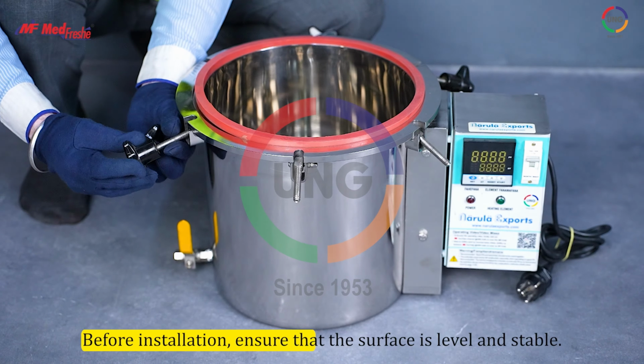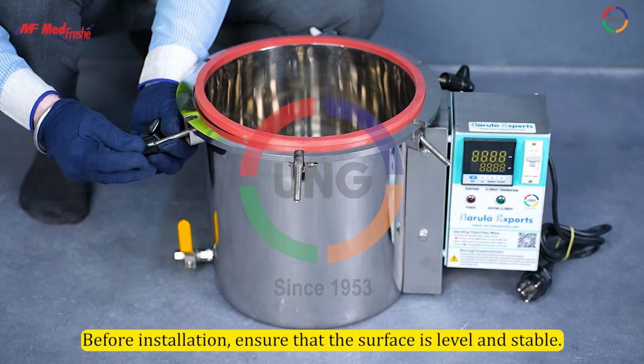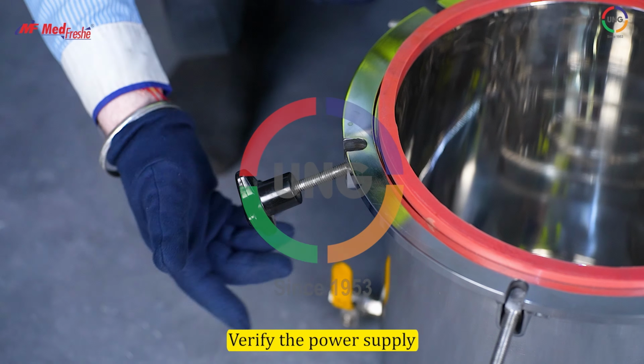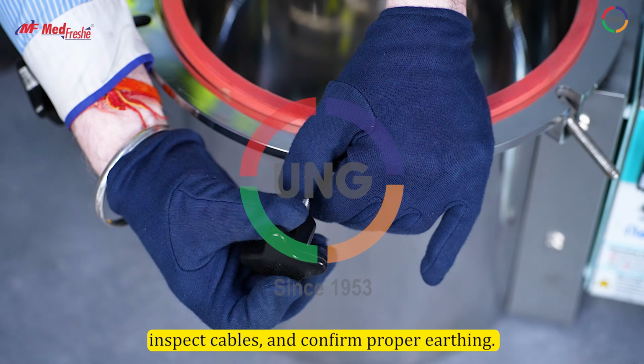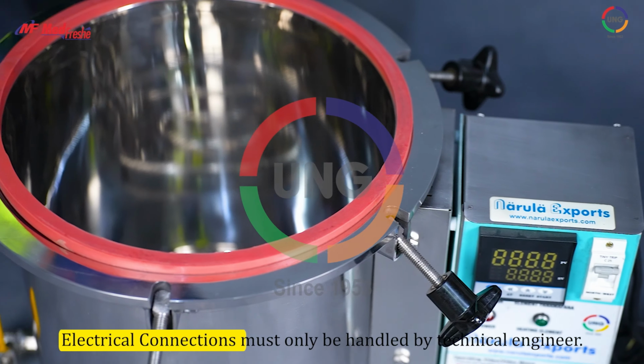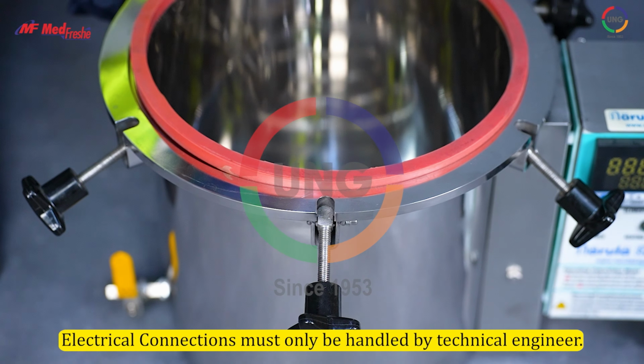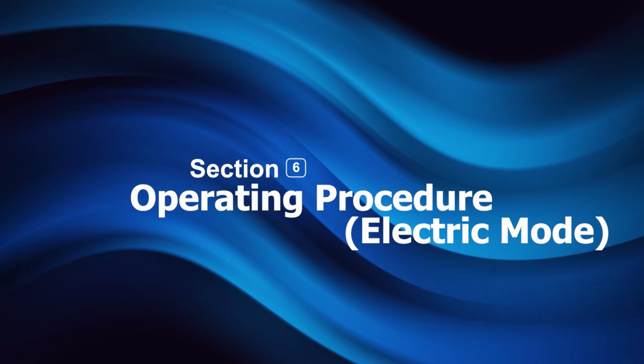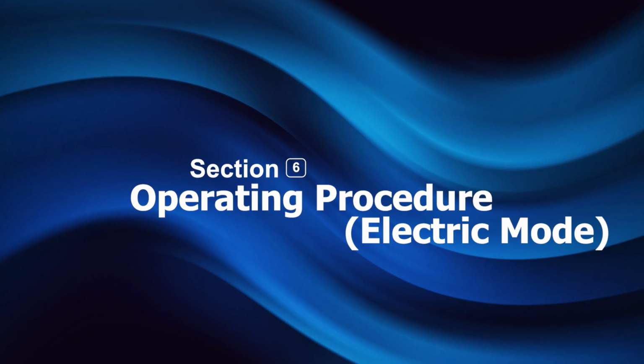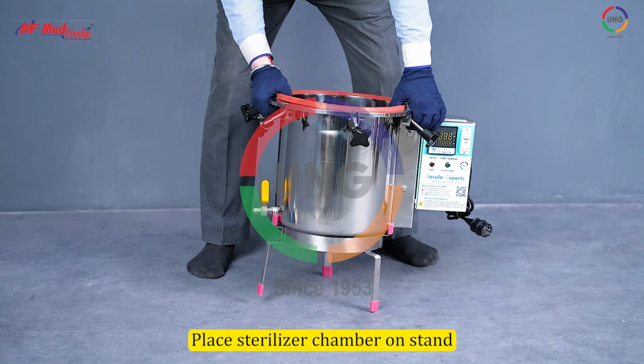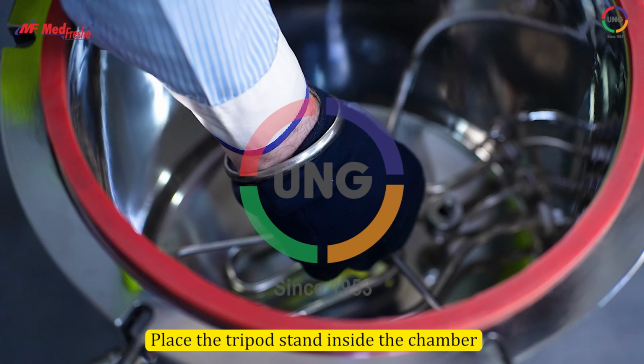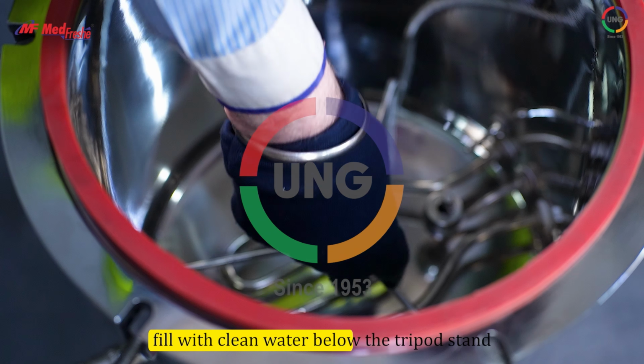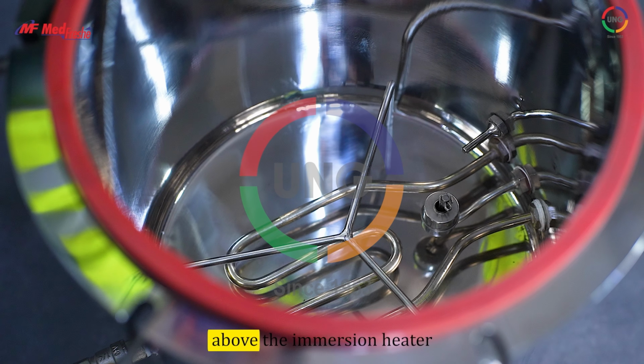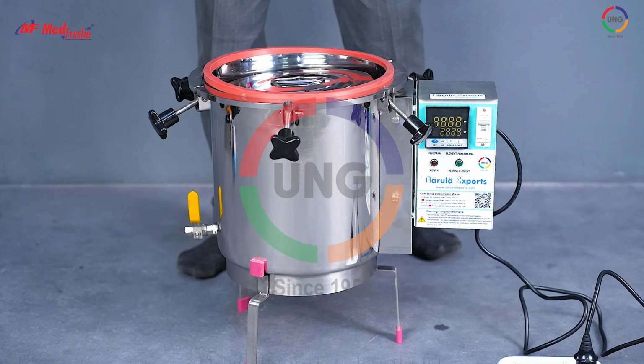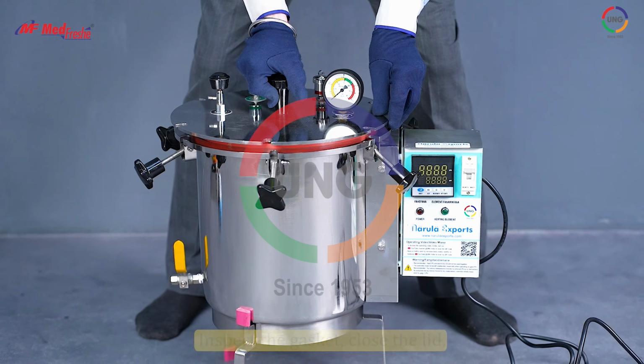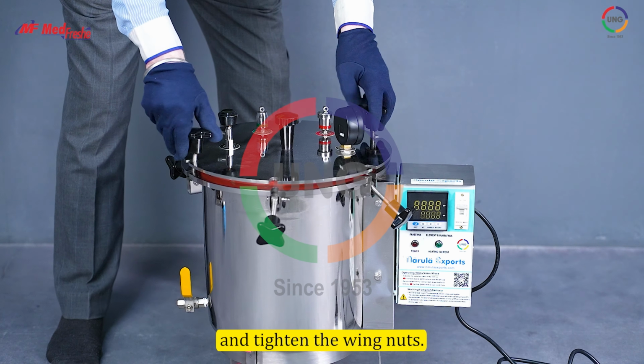Before installation, ensure that the surface is level and stable. Verify the power supply, inspect cables, and confirm proper earthing. Electrical connections must only be handled by a technical engineer. Section 6, Operating procedure, electric mode. Place the sterilizer chamber on the stand. Place the tripod stand inside the chamber. Fill with clean water below the tripod stand and above the immersion heater. Inspect the gasket, close the lid, and tighten the wing nuts.